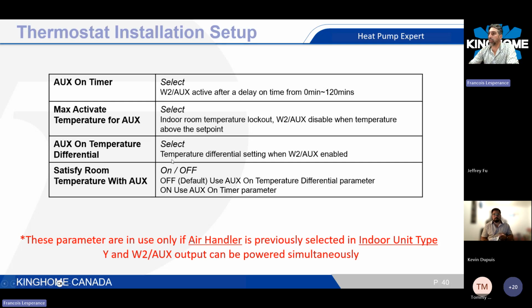But we can give you the definition on every setup there. So aux on timer is really a delay for whenever you want to start the heat strip with the heat pump, because this is the big difference between those two setups: when you have an air handler, you can use your heat pump and your heat strip powered simultaneously. So basically, they can run together. So Y terminal and aux terminal can be powered at the same time. So we can add a timer, a time delay from 0 to 120 minutes, sorry, to call for the backup heat to be engaged.